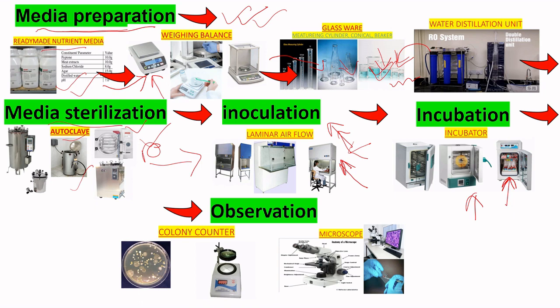In the incubator, a particular temperature and time is maintained for incubation of the microorganisms. For example, some bacteria require 37°C for 24 hours, while different microorganisms may require 42°C or 25°C for 24, 48, or 72 hours. Different microorganisms require different incubation conditions for their growth.